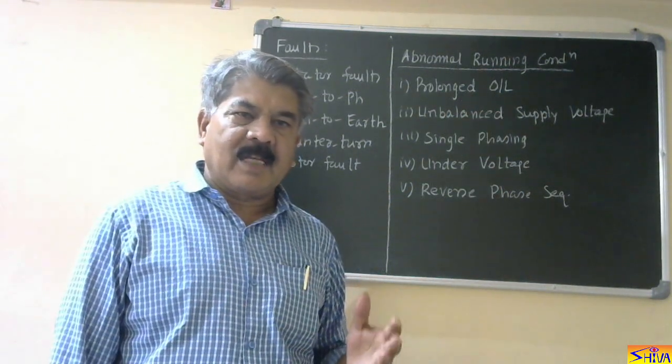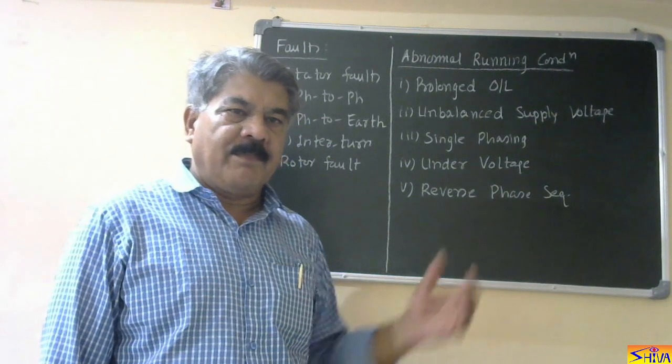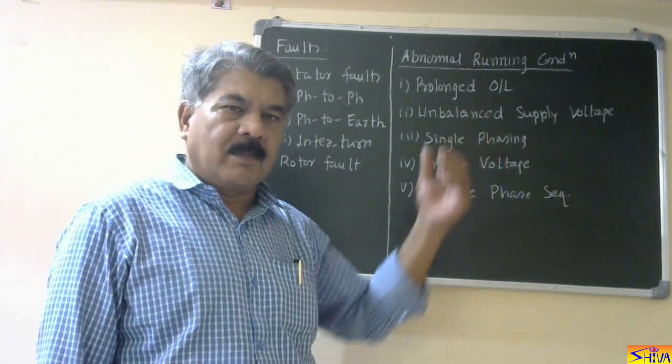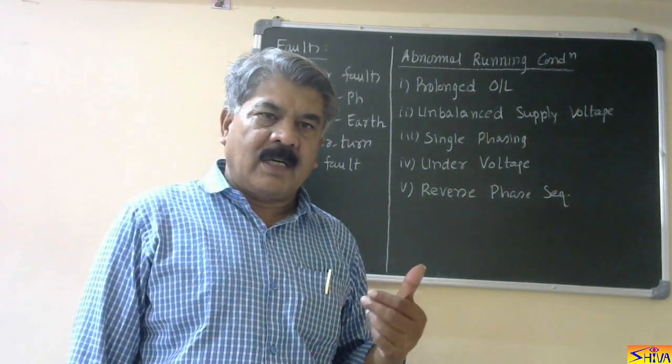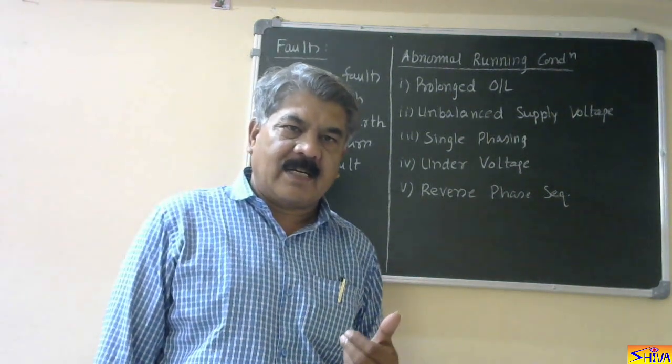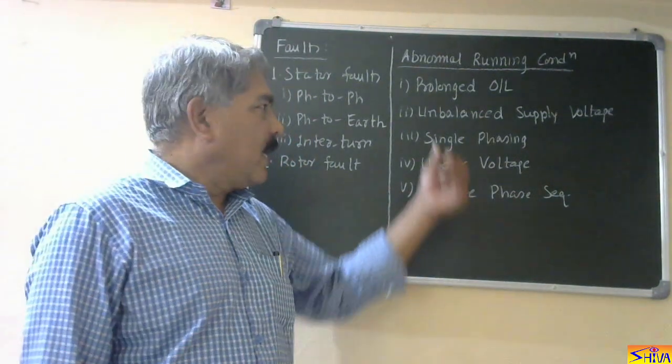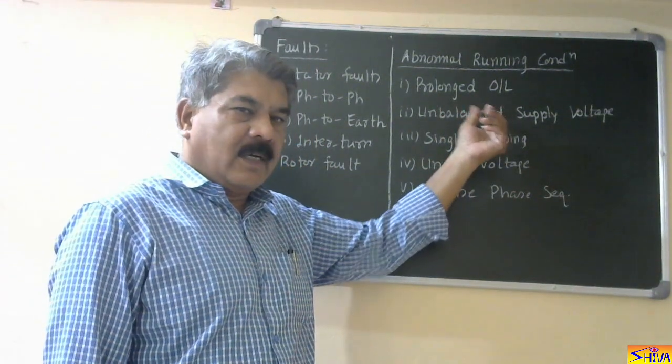If it is a medium sized motor, then thermal overload relay will detect this fault. Thermal overload relay means it is temperature sensing, temperature increases due to current, and it has inverse characteristic like IDMT relay. So that detects the prolonged overload condition.